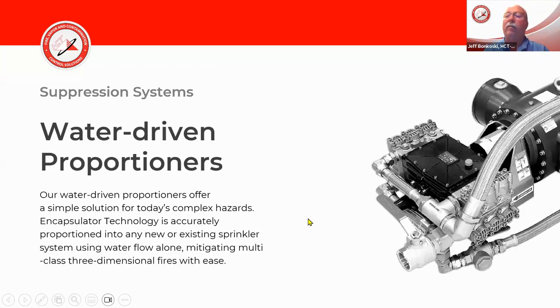But one of the other more effective and efficient ways is water-driven proportioners. And I'm going to tell you, when you look at those bladder tanks, they're good, but as I said, there are problems with the bladders being damaged for different reasons. The other thing is when we have a system that has a riser and it's dealing with, let's say, 8 or 10 sprinkler heads, if the system is designed to flow 3%, it might not be at 3% if half of those sprinkler heads go off.